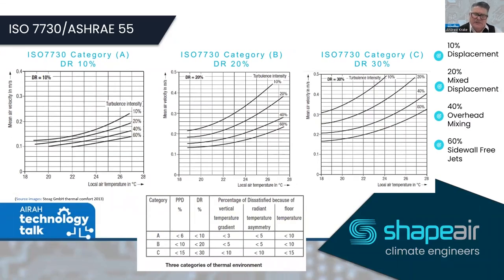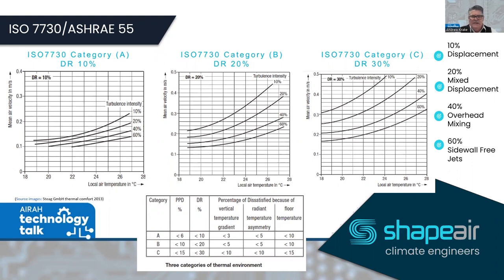The ISO 7730 velocity movements are created around the draft rating, which is a full calculation of floor temperature, radiant temperature, velocity gradients, terminal velocities, and turbulence intensity. There are three ISO categories: Category C is a draft rating of 30%, Category B is 20%, and Category A is 10%. These relate to the types of air diffusion equipment and systems being installed.